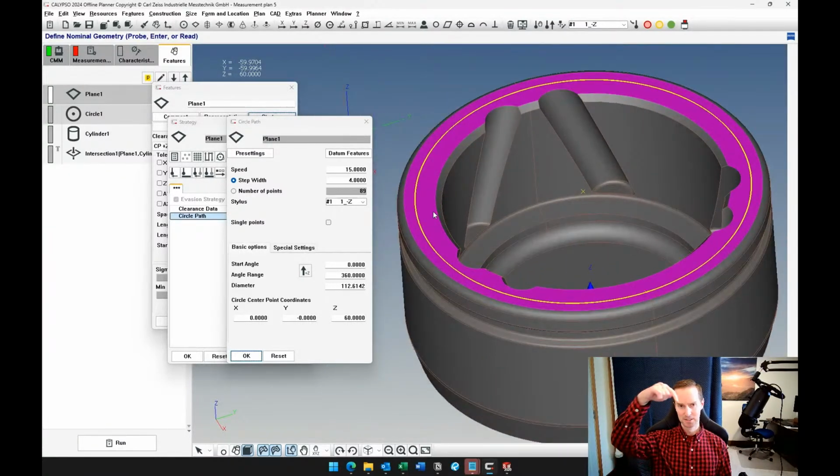And I always tell people when you're scanning something with a probe going straight down on a plane, you want that speed to be less than you would use on a cylinder, because imagine if you take a pencil with the eraser on the paper and you press and slide it. It's not going to slide very smoothly. It's going to kind of bounce on that paper.